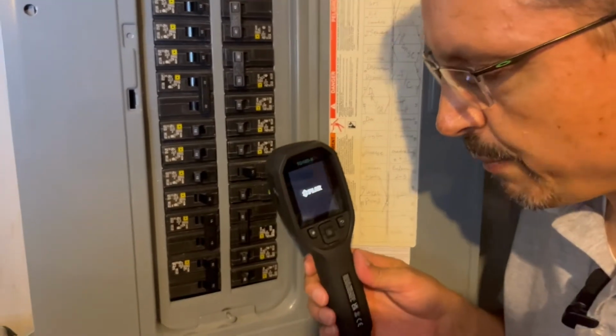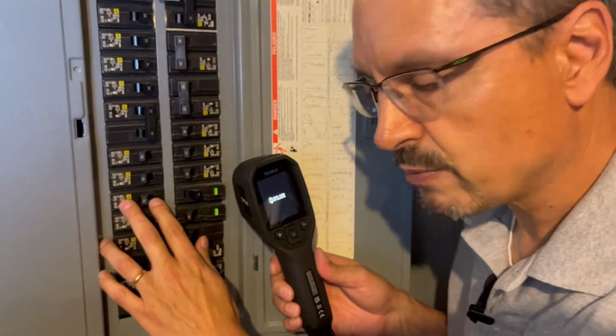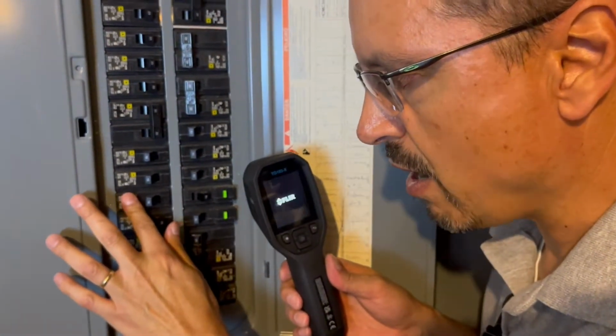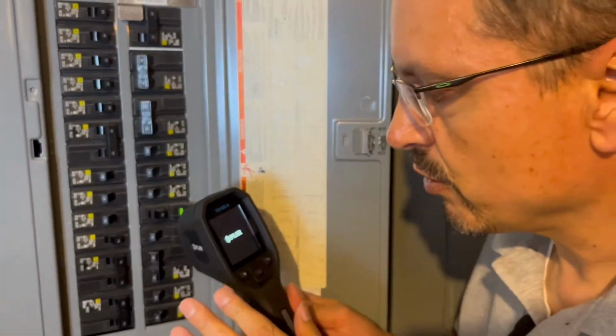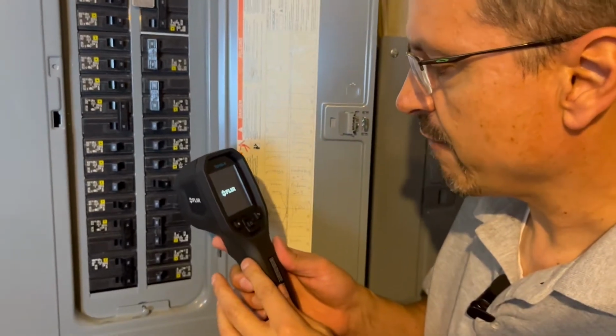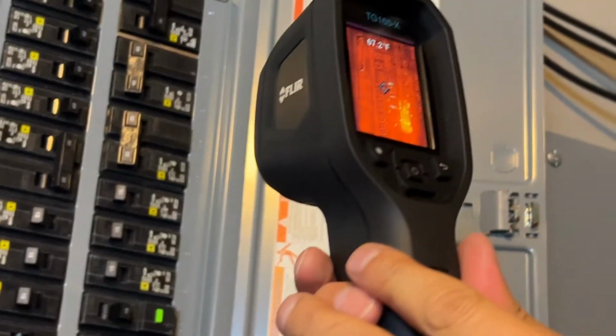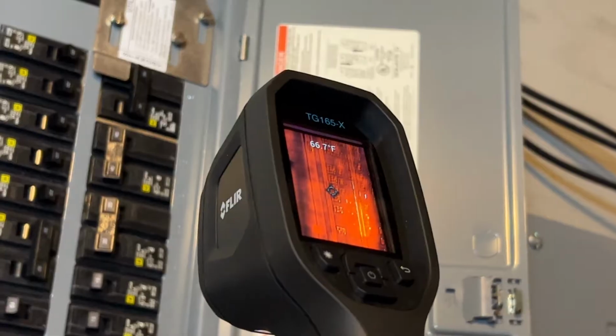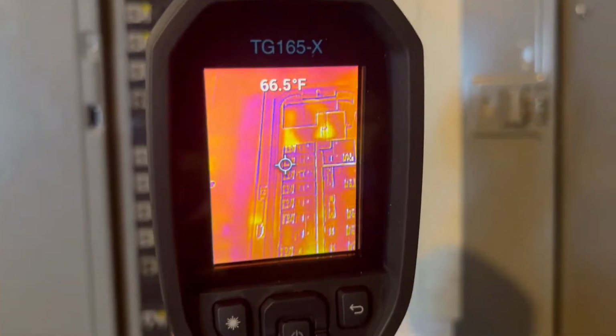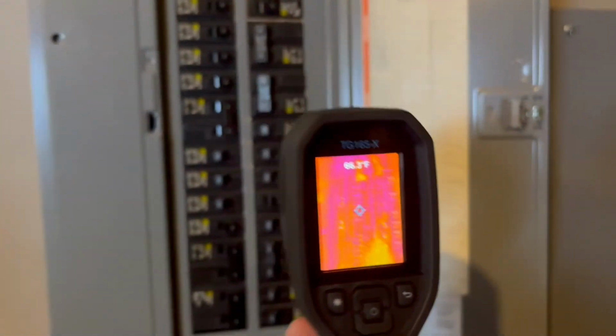Another reason to replace a circuit breaker that you suspect is going bad is if it's warming up. You can use a temperature device. This is a FLIR infrared temperature sensor, and you can actually use it to check any hot spots in your panel box. It's a really neat device. If you don't have one, maybe you can borrow one from your builder friends.